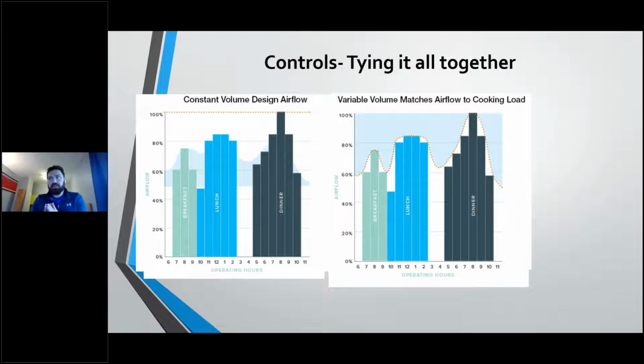Variable volume systems are going to do exactly what they sound like. They are going to vary the volume of the system, typically based on some sort of temperature basis or a combination of temperature and optic sensing. This is going to vary the speed of the fans as cooking operations go up and down. If you think about a traditional restaurant, you're going to have your prep time in the morning. The chef's going to come in at 10 a.m., and they're going to start the appliances, and then they're going to go in back and start chopping up the onions and doing all that prep work. Well, the appliances are running, so the fans are going to need to be running at some sort of minimum speed, but they don't need to be running at 100% of design.